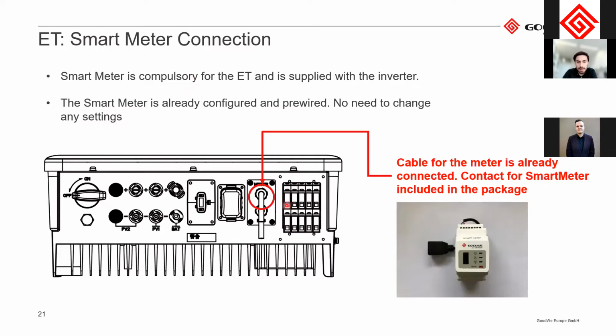After that, you need to connect a smart meter. This is compulsory for all hybrid inverters. The smart meter helps the inverter to know how much load is being used to optimize the discharge and charging of the battery. On both the old and the new ET inverter, there is one port here just next to the AC output called meter, and everything here is already pre-wired. I will show that later as well.